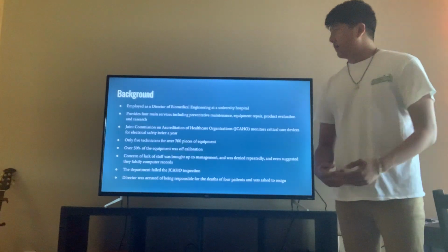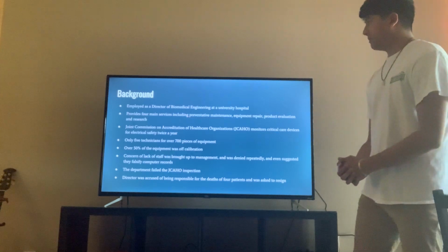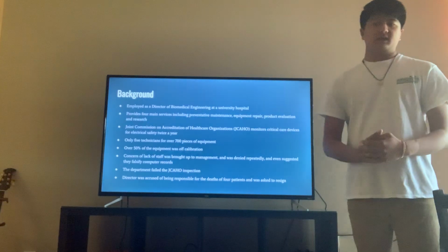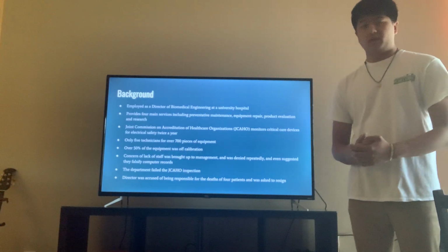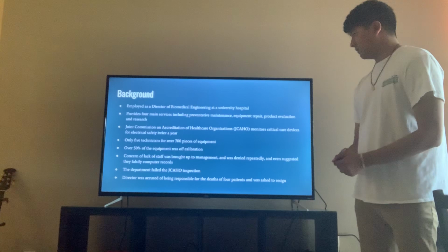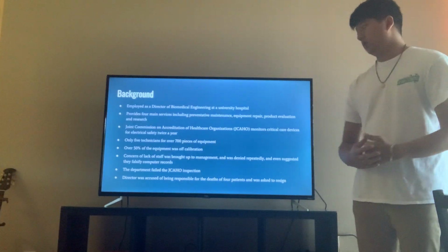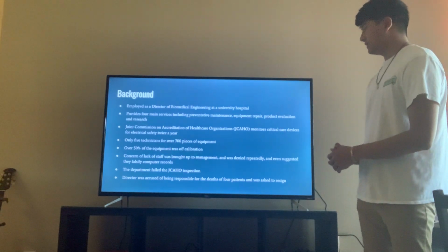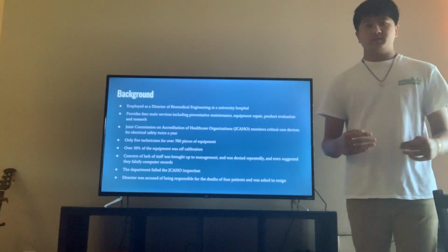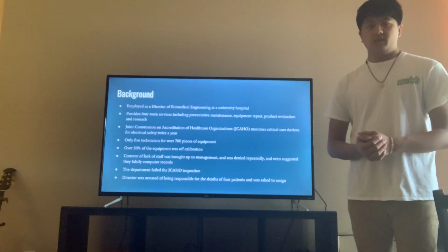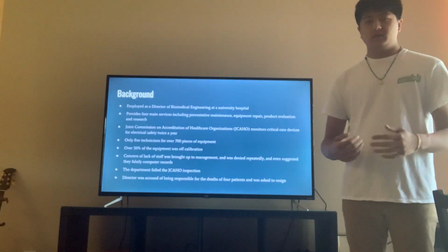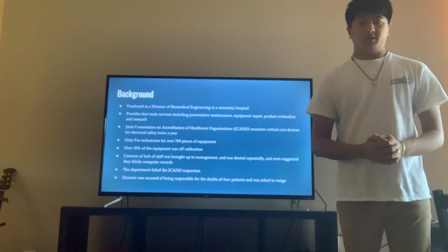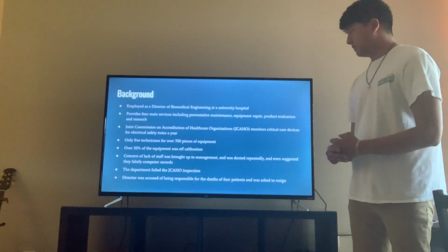So as a general background, what happened was it was from the point of view of the director of biomedical engineering at a university hospital. He was tasked with being in charge of preventative maintenance and repair of over 700 pieces of equipment in the hospital, along with his 5 technicians. Now, the Joint Commission on Accreditation of Healthcare Organizations monitors critical care devices in the hospital, and they have to come by every 6 months to complete an inspection. So all the equipment has to be calibrated by then.